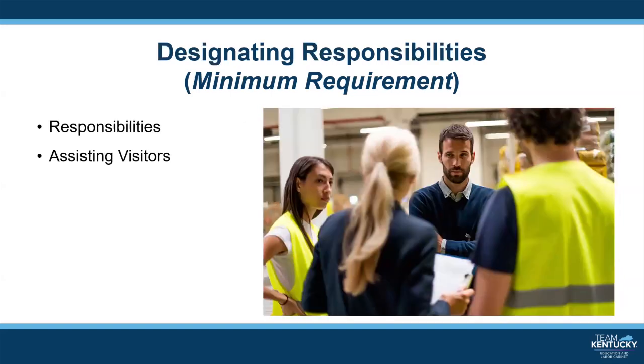Many employers designate individuals to help move employees from dangerous areas to safe areas in an emergency. Generally, one designated person for every 20 employees should be adequate, and the appropriate number of designated persons should be available at all times during work hours. A designated person may be responsible for checking offices, restrooms, and other spaces before being the last person to exit an area. They might also be tasked with ensuring that fire doors are closed when exiting.